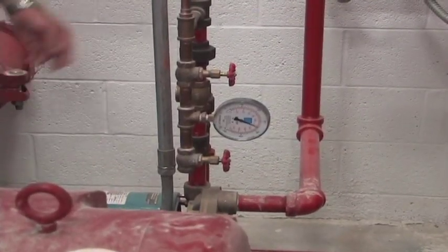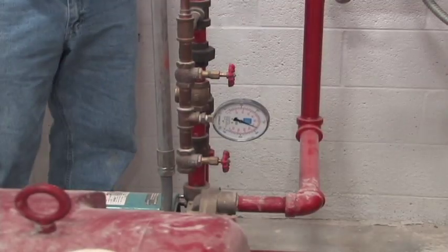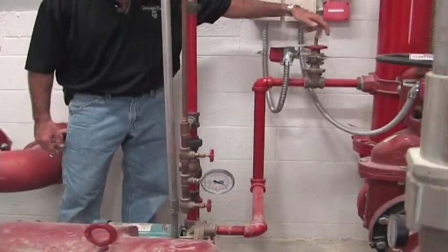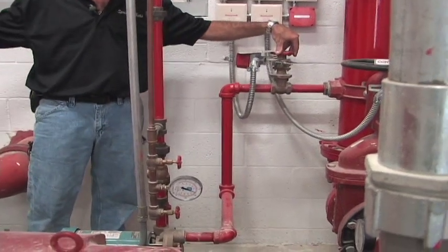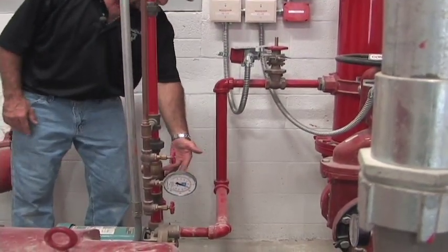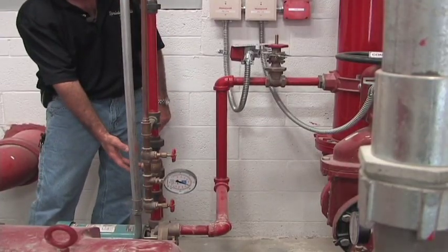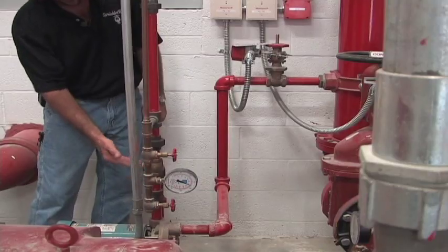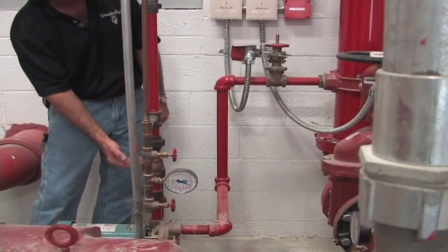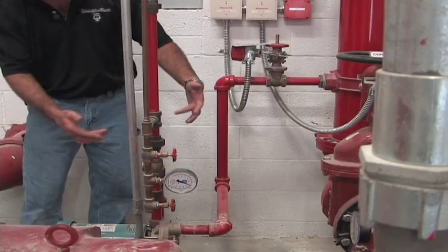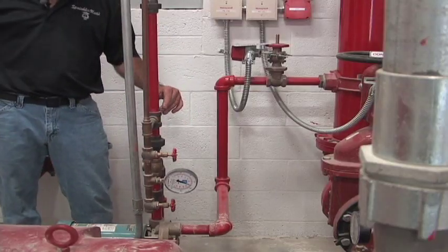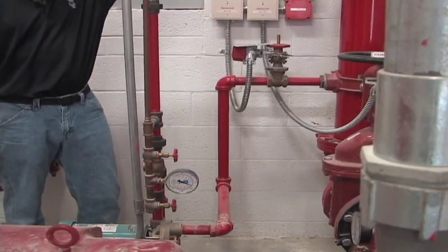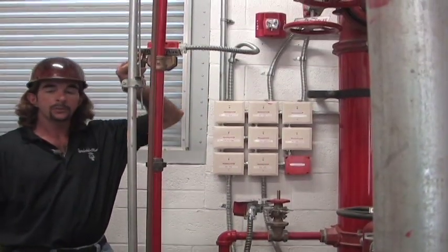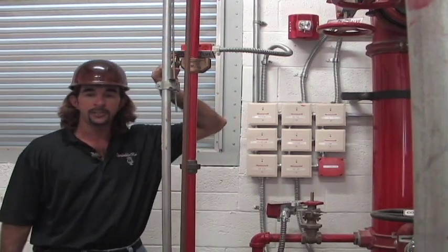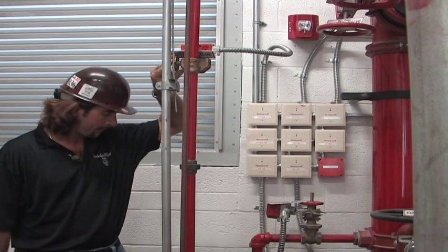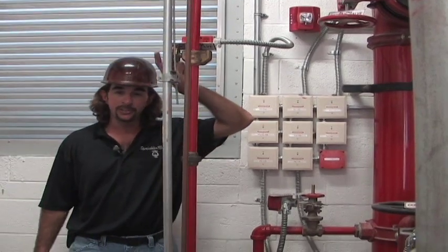The jockey pump, just like the fire pump, has a supply valve with a tamper. When closed, it will send a trouble or supervisory signal to the alarm panel. You've got a check valve also, which is a one-way directional valve. When the jockey pump's up, pressure above here will remain. You have city pressure down below it, and you have building supply pressure past this. We have our sensor line, which feeds our jockey pump and tells it when to turn on and turn off. And then we have our discharge control valve. Naturally, when it's closed, we will have a trouble or a supervisory at the fire alarm panel saying jockey pump discharge valve is closed. That's pretty much the standard and basic operations of the jockey pump.